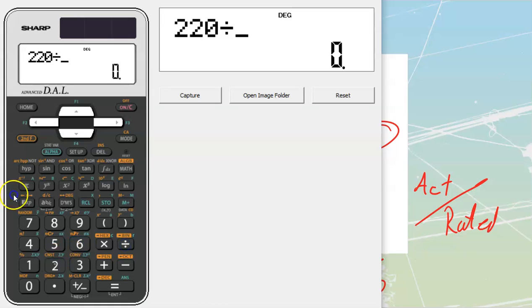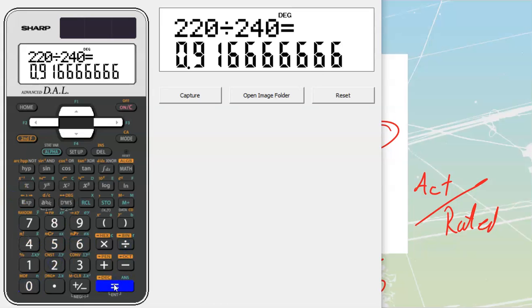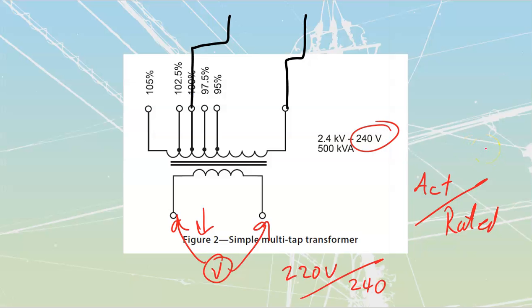220 divided by 240, which gets me to a value of 91.6. I'm coming in at only roughly 92%. So what I'm going to want to do is move my taps to that, because that's the percentage of volts that I'm currently at.